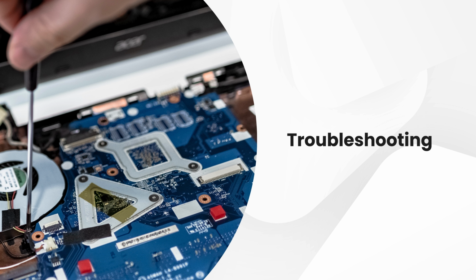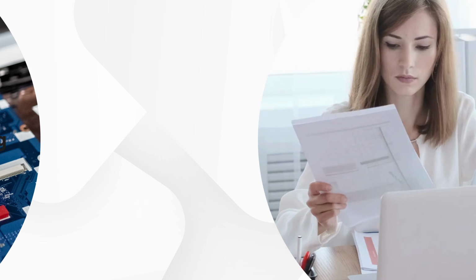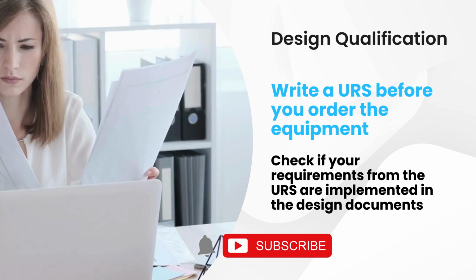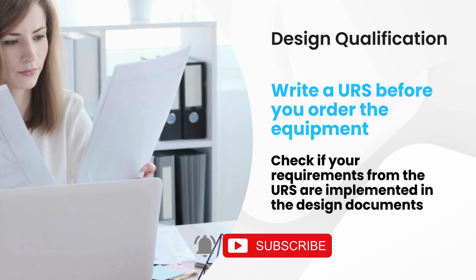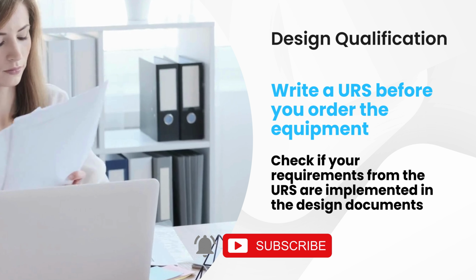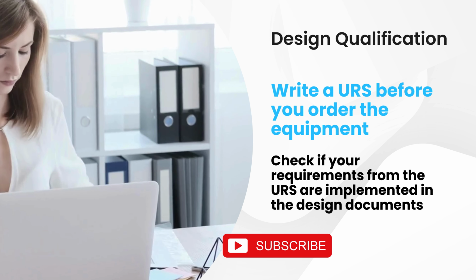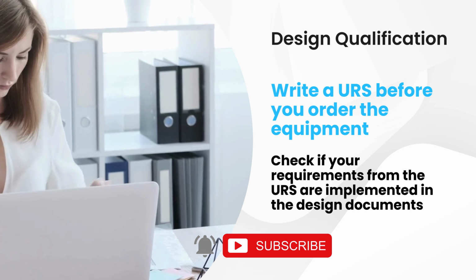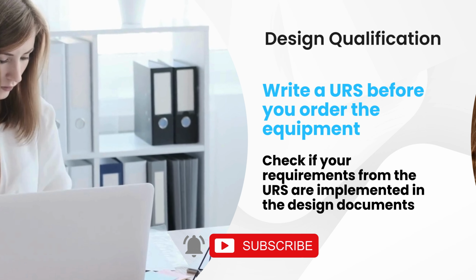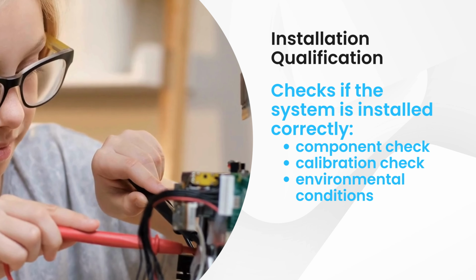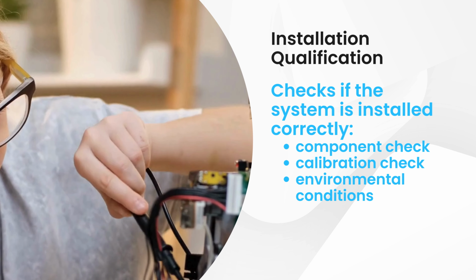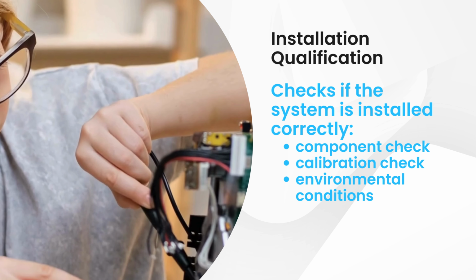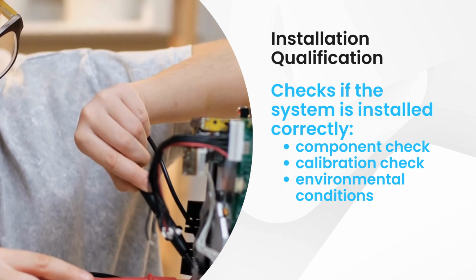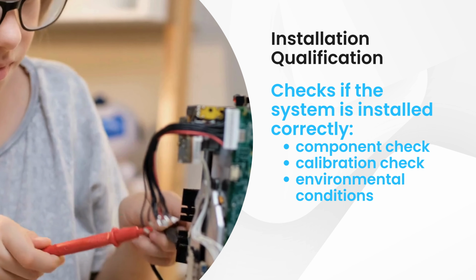1. Design qualification, DQ. This confirms that the HPLC system you select meets your specific requirements and intended use. It's like checking if you bought the right tool for the job. 2. Installation qualification, IQ. This verifies that the HPLC system is installed correctly according to the manufacturer's specifications. This includes proper connections, environmental conditions, and software installation.